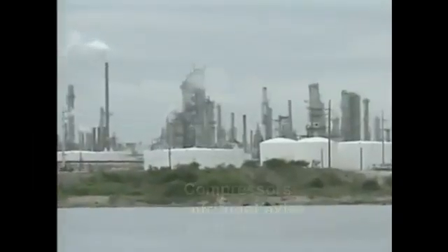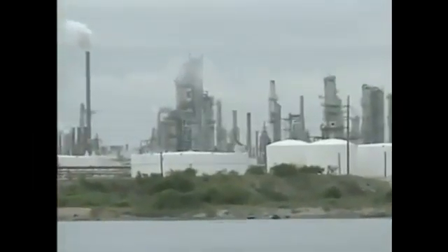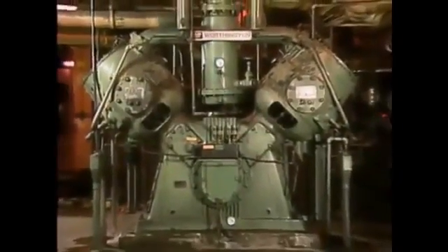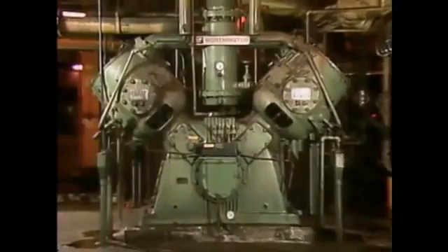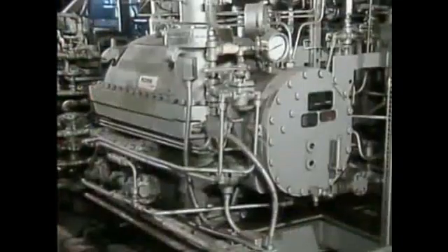Compressors are used in industrial facilities to increase the pressure of air or other gases. The basic types of compressors are positive displacement compressors, centrifugal compressors, and axial compressors. When centrifugal compressors and axial compressors increase the pressure of a gas, they first increase its velocity. The gas is then slowed down and its velocity is converted into pressure.